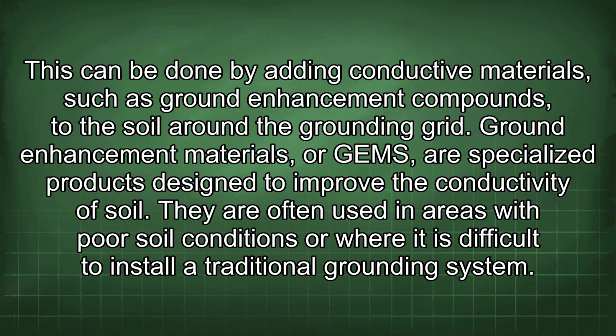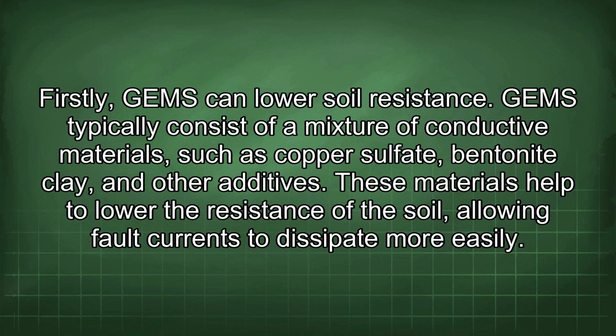Ground enhancement materials, or GEMs, are specialized products designed to improve the conductivity of soil. They are often used in areas with poor soil conditions or where it is difficult to install a traditional grounding system. Firstly, GEMs can lower soil resistance. GEMs typically consist of a mixture of conductive materials such as copper sulfate, bentonite clay, and other additives. These materials help to lower the resistance of the soil, allowing fault currents to dissipate more easily.